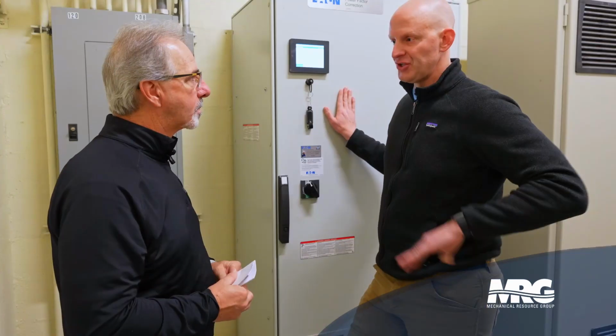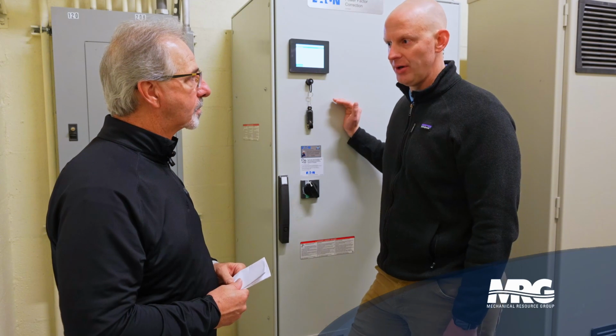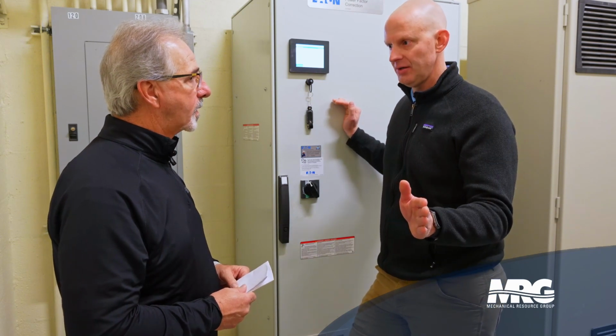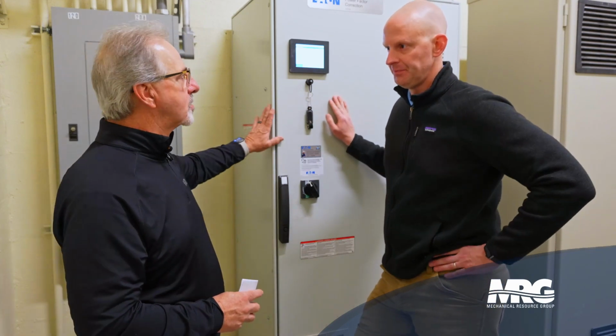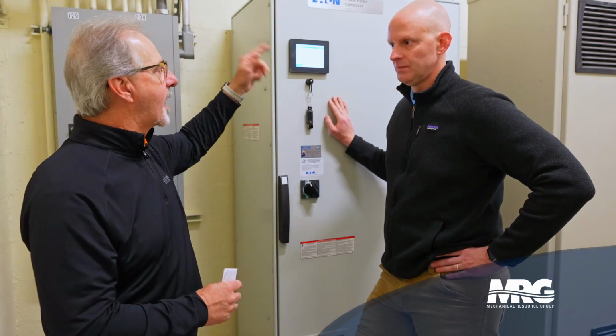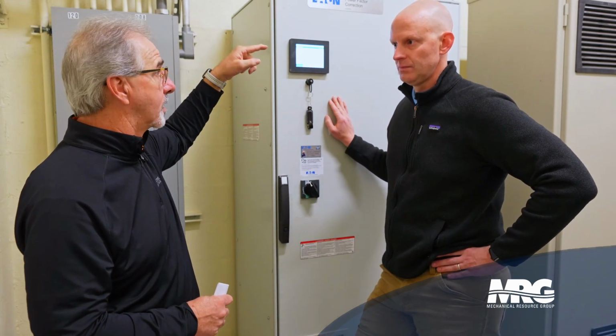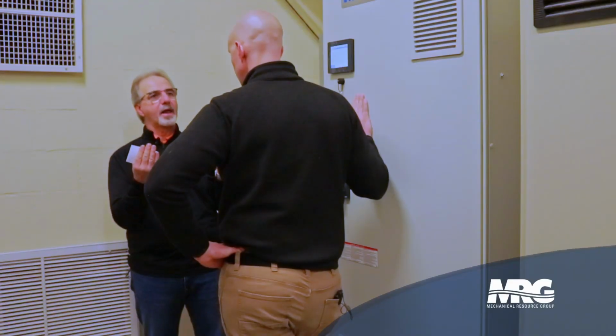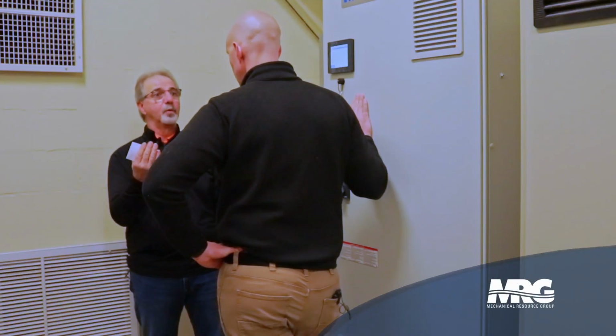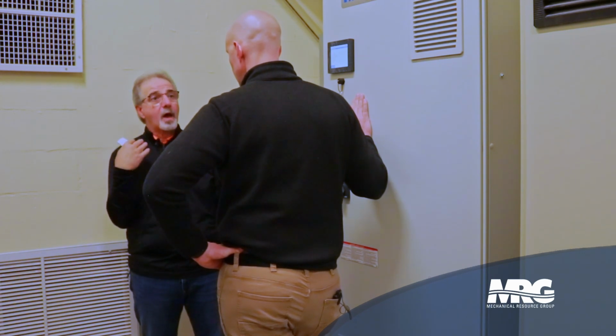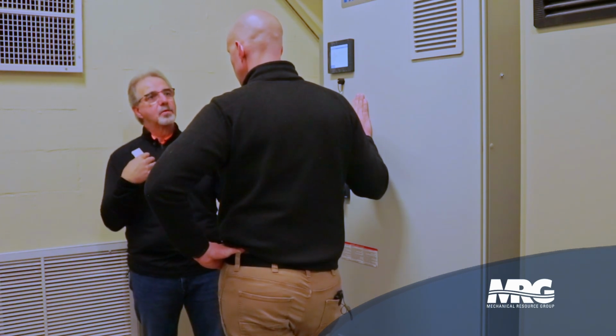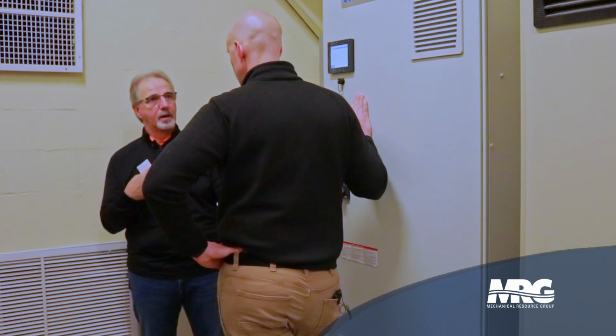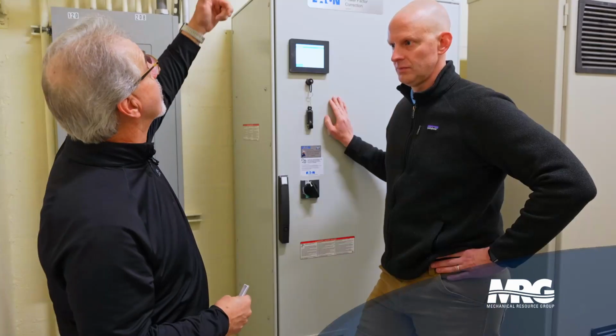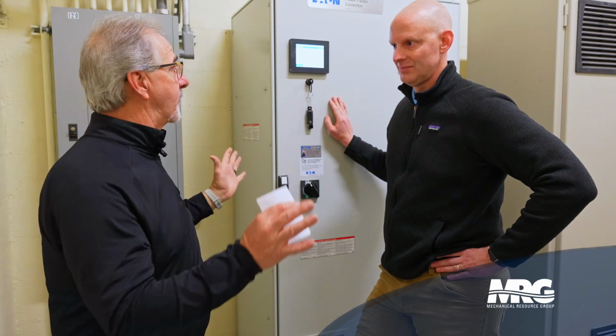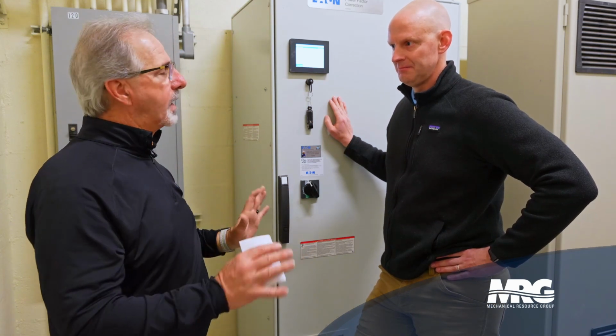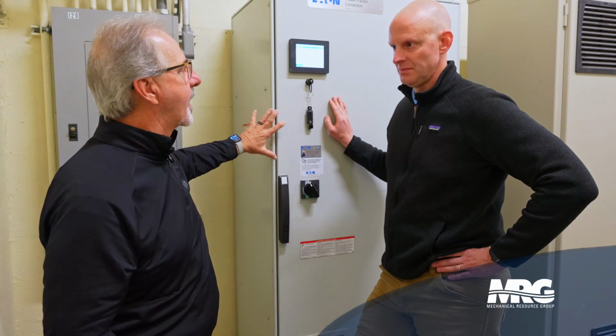If the generator's running, are we cleaning that power with the filter back to the generator? Yes, we are. Or are we worried about that? Yeah, the filter is always in the circuit. The ATS is right off the generator as well as the outside utility transformer. It comes into an automatic transfer switch, and it doesn't matter. If we lose power, the transformer is offline, obviously, and then it syncs up the generator. The generator comes online. If you'll notice, the main power comes in and drops into the filter before it hits anything. Yeah. So anytime we are running drives, we are on the active filter.